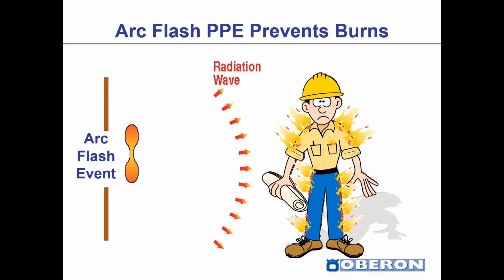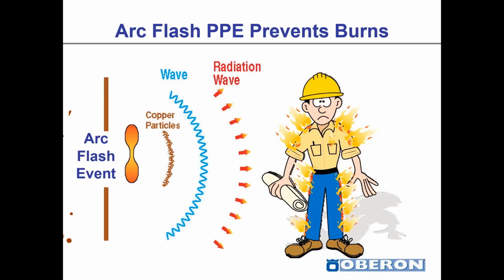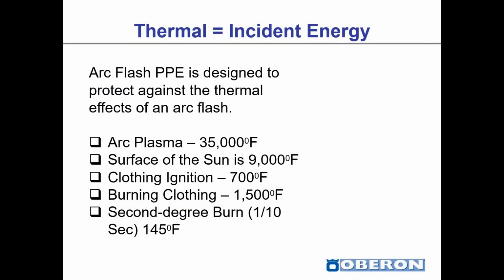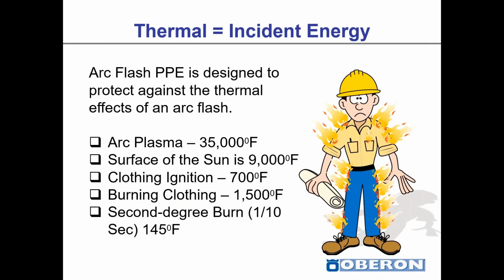In terms of how it works, Arc Flash PPE prevents the burns. We have the initial stage of an arc flash event being the radiation wave. We have a pressure wave that follows, and often we have debris that is being shot at ballistic velocities at the worker, such as copper particles. The thermal energy equals the incident energy, that is the calculations, and the partners here at EasyPower do a great job in terms of helping you do those calculations to determine what PPE is needed. So identifying the severity is part of the risk assessment.